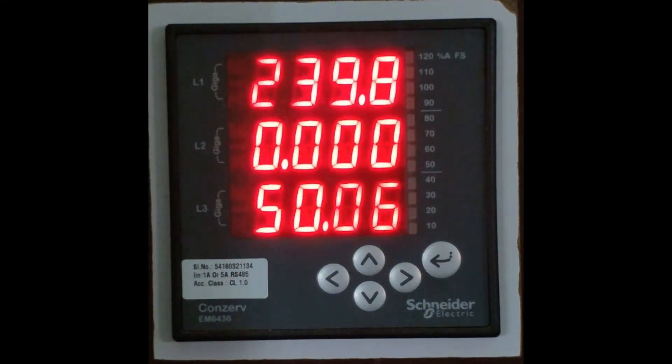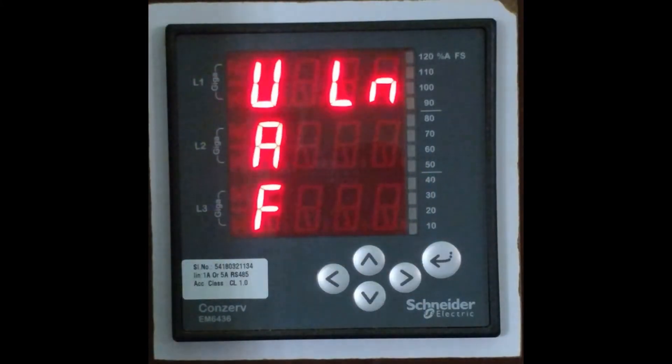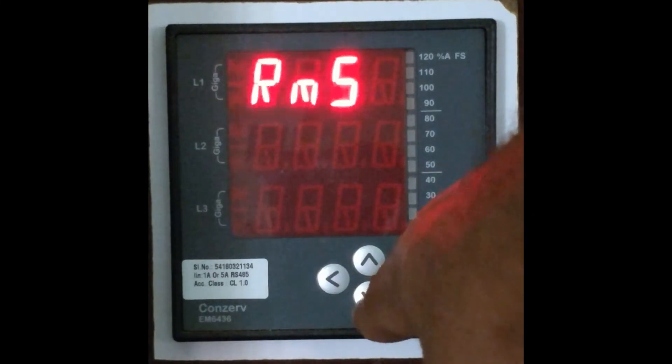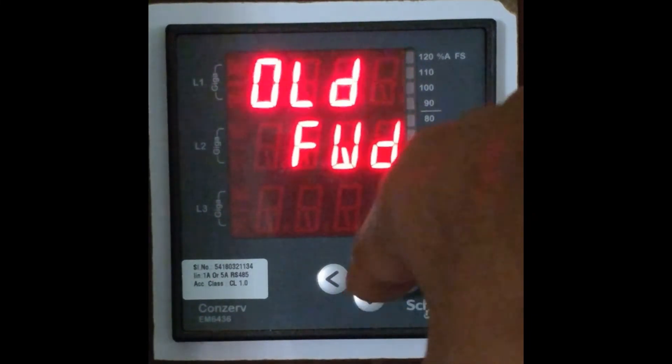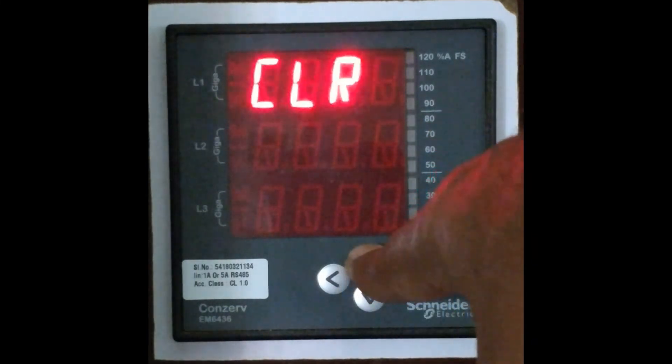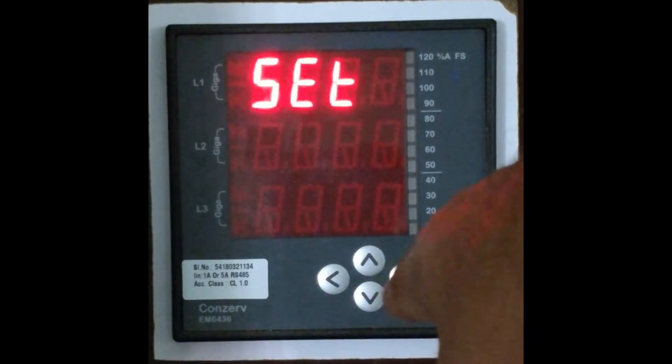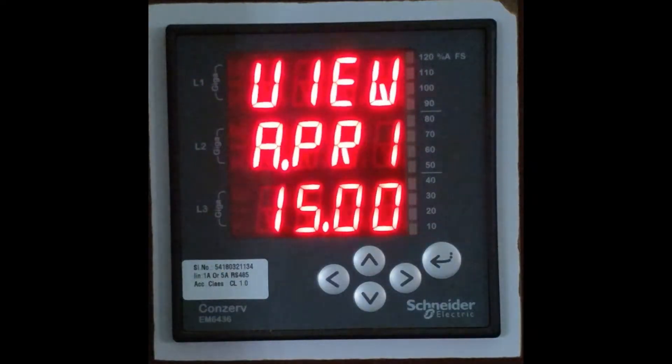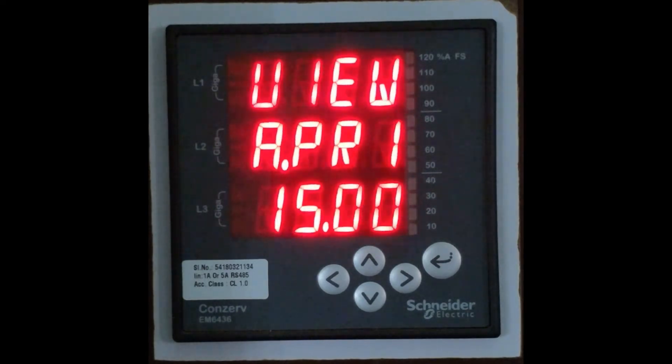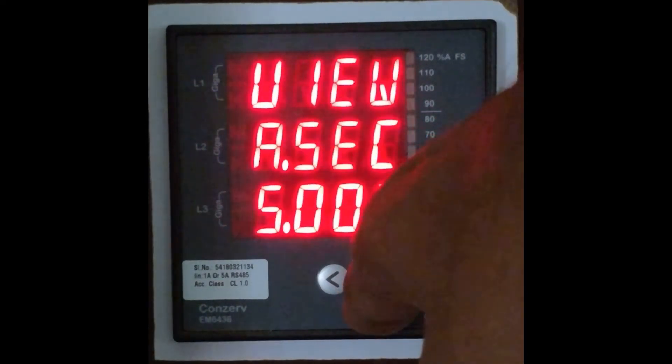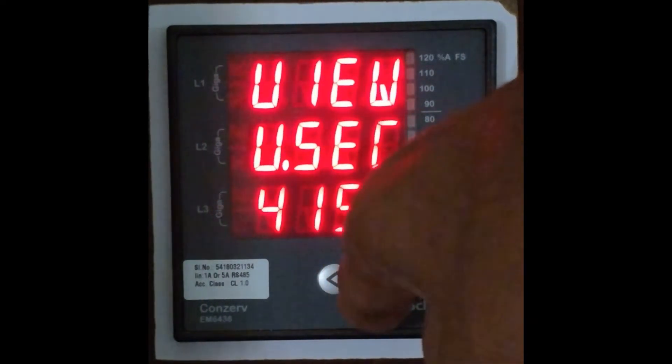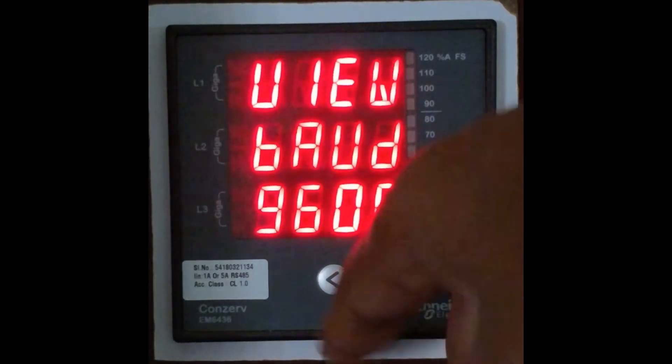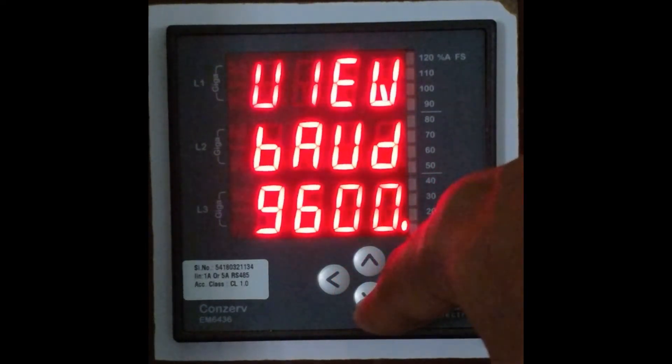So once you have such a meter, there are a few things that we want to see regarding the communication aspect. We will see what is the current configuration of the smart meter in terms of communication. We will have to check the configurations for communication aspects - basically the baud rate, the parity bit, and all. If we see these are the electrical part, we will move on to the communication part. You can see the baud rate is currently set at 9600.